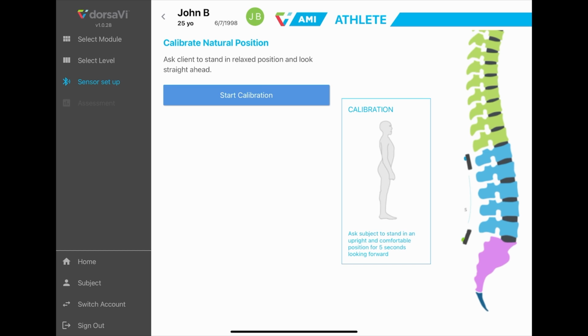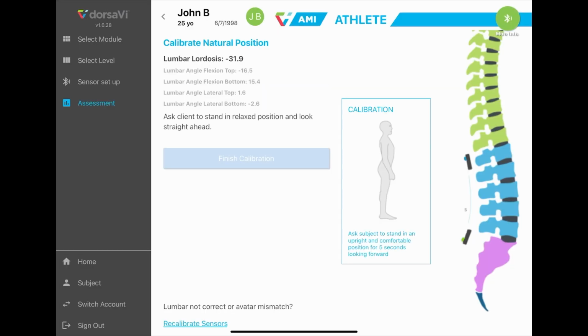Ask your subject to stand in an upright and comfortable position for 5 seconds looking forward. Press Start Calibration. This subject's lumbar lordosis is negative 31.9 degrees. You should always see a negative number. Negative means extension, and when we're standing, we will always start in an extended position.